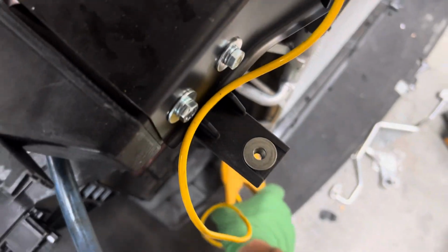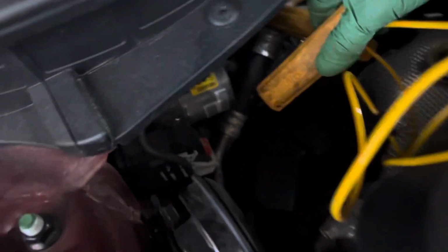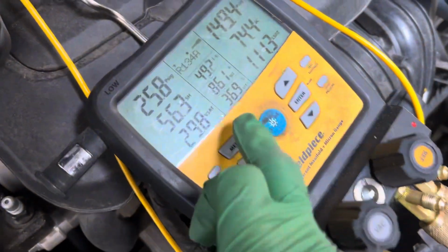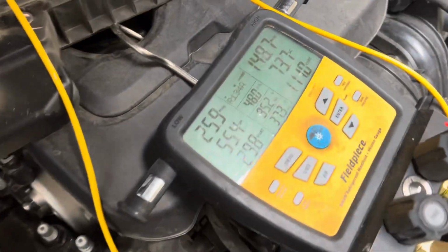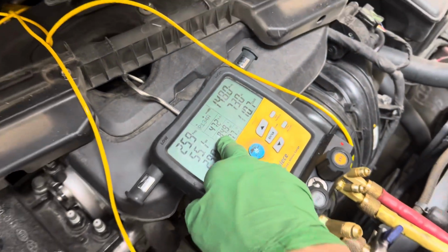So now let's take it off of there, and let's put it after, and take right there. There we go. Now we're after the internal heat exchanger. So now it's been subcooled. Let's see what temperature that liquid has dropped down to. Did I do that right? Where's that guy? Let me make sure. 85 degrees.